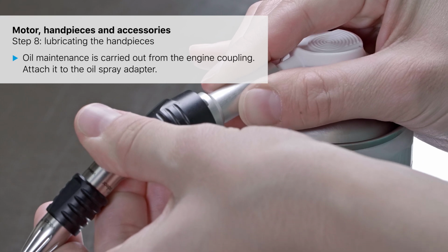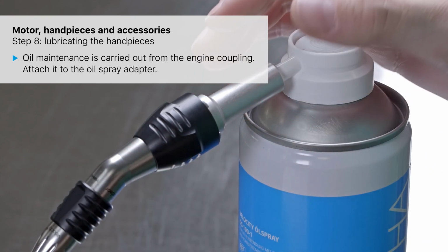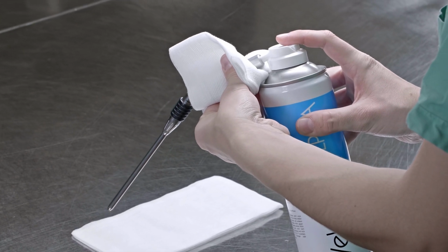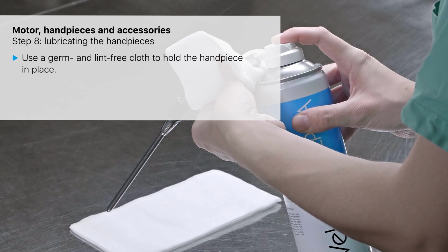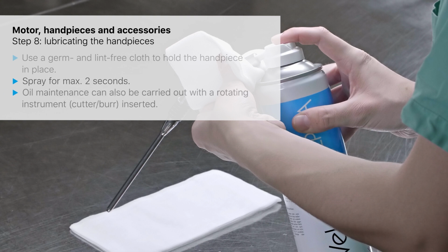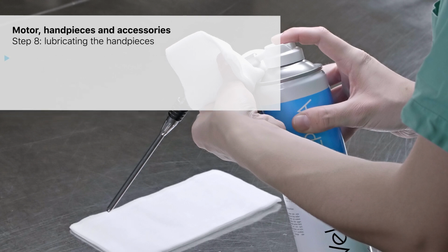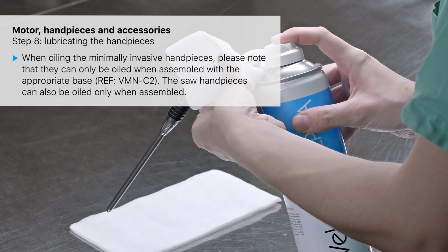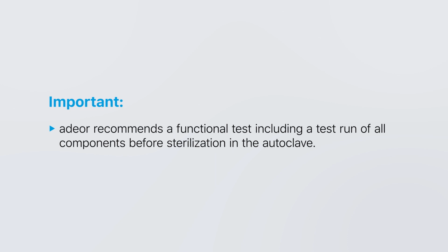Oil maintenance is carried out from the engine coupling. Attach it to the oil spray adapter. Use a germ and lint-free cloth to hold the handpiece in place. Spray for max 2 seconds. Oil maintenance can also be carried out with a rotating instrument, cutter, burr, inserted. When oiling the minimally invasive handpieces, please note that they can only be oiled when assembled with the appropriate base, reference VMN-C2. The saw handpieces can also be oiled only when assembled. Important: adeor recommends a functional test, including a test run of all components before sterilization in the autoclave.